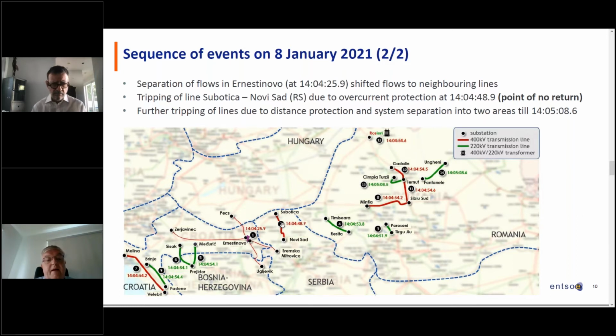Then number two, at 14:04:48, you have a line in Serbia which was not supposed to be overloaded, but in reality it turned out to be overloaded. It turned out to take more flow than was originally estimated and calculated, and so this line went into overload, and a 20-second relay disconnected the line Novi Sad-Subotica. Of course, then there are already two important lines transporting power to the rest of Europe from the Balkan area which are disconnected.